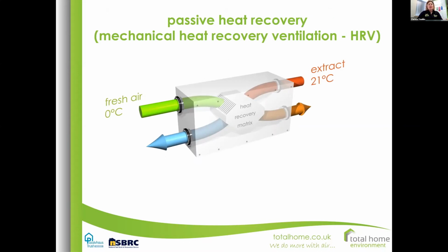So if we look at how this works with regards to temperature, if the air outside is 0 and it's 21 degrees inside the house, you can expect to recover enough heat from this stale air to put this fresh air into your supply rooms at 17 degrees, which means that any heating system that you've got has only got to find that 4 degrees difference. Whereas with any other form of ventilation, opening a window, trickle vents, etc., it's whatever the temperature outside is that your heating system has got to cope with.